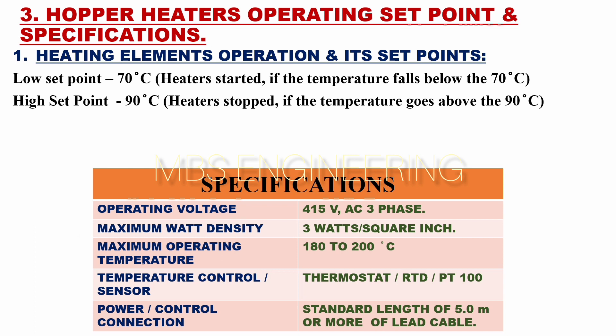The maximum operating temperature is 180 to 200 degrees Celsius. For temperature control, sensor heating elements such as thermostats, RTD, or PT100 are used for temperature transmitter and control purposes. Regarding power and control connection, the power and control cables are supplied with a standard length of 5 meters and more based on requirements.